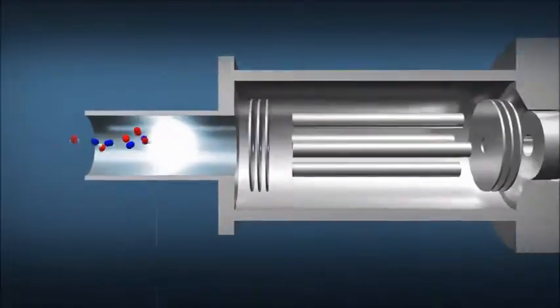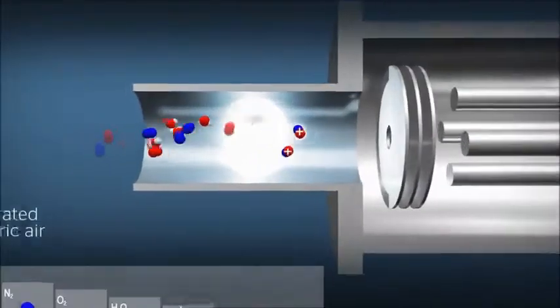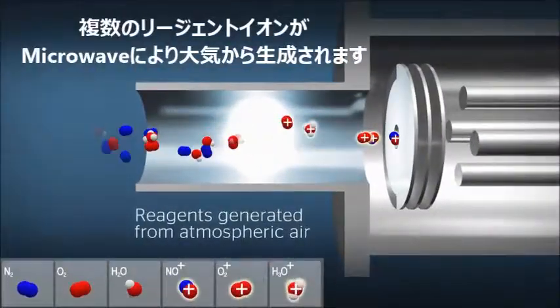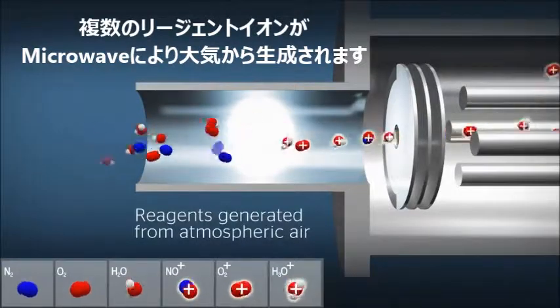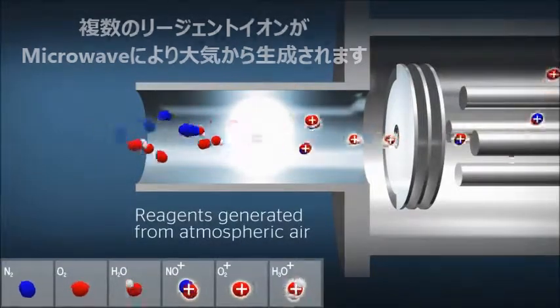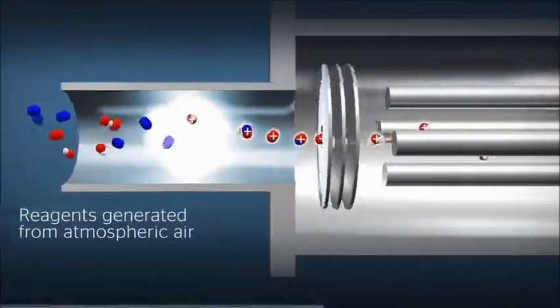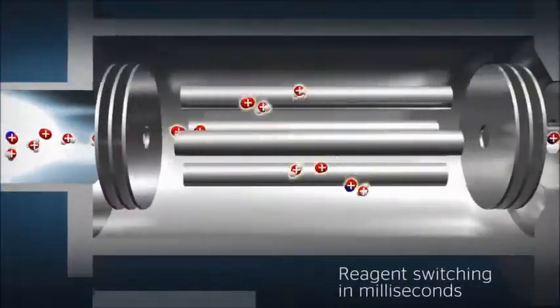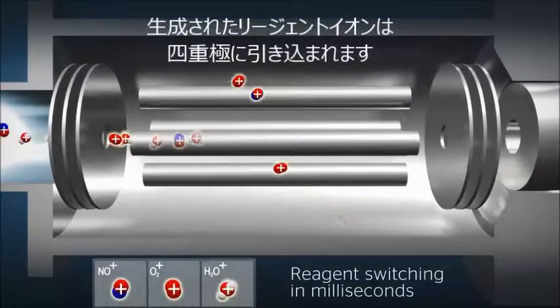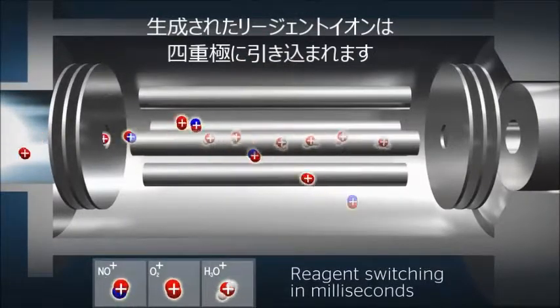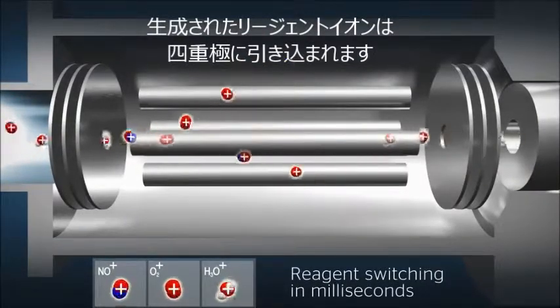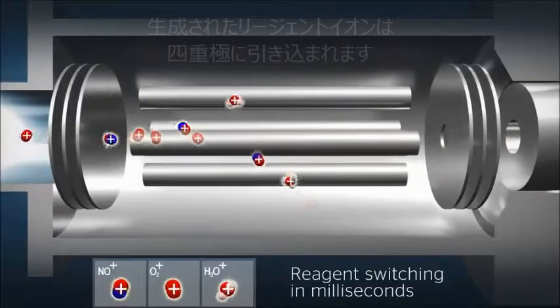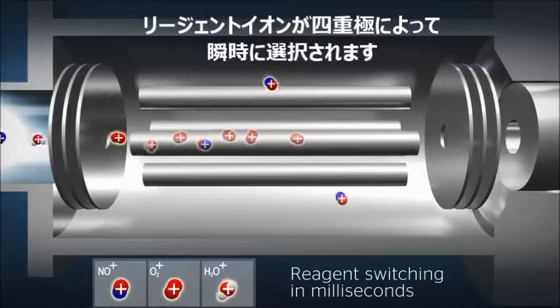Air and water vapor pass through a microwave discharge to produce multiple reagent ions. These reagent ions are focused into a quadrupole mass filter. Inside the quadrupole, reagent ions are filtered by their mass-to-charge ratio.